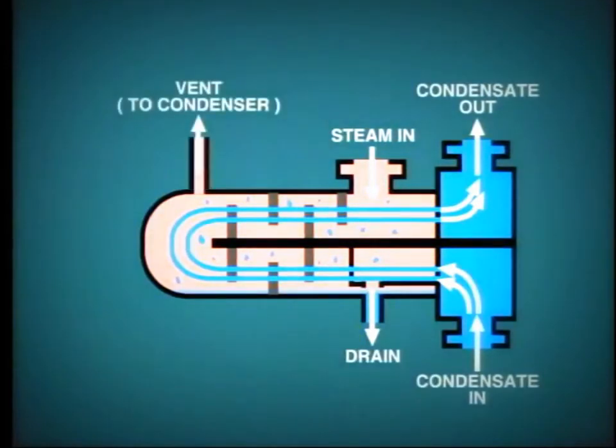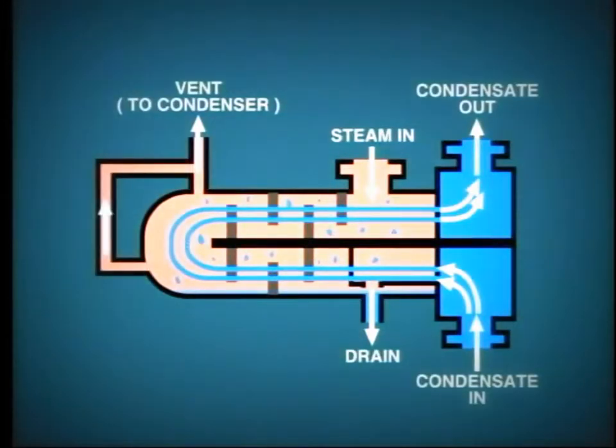In practice, vents are fitted at both the top and intermediate level of the heater. The reason for this is that air finds its way to the top of the heater, while carbon dioxide remains at the lower level just above the water level.